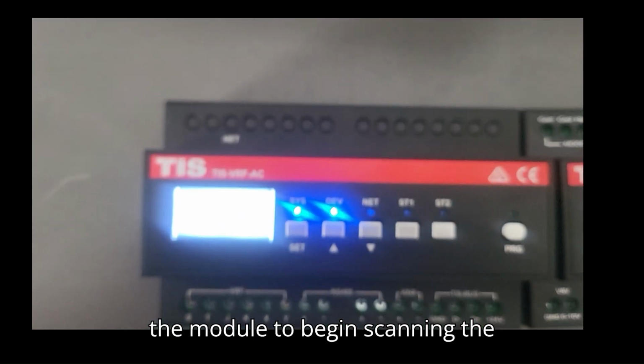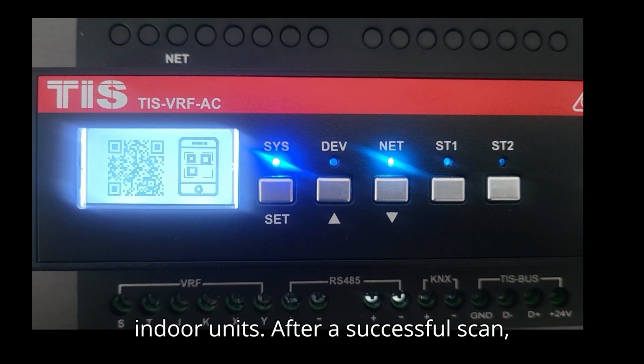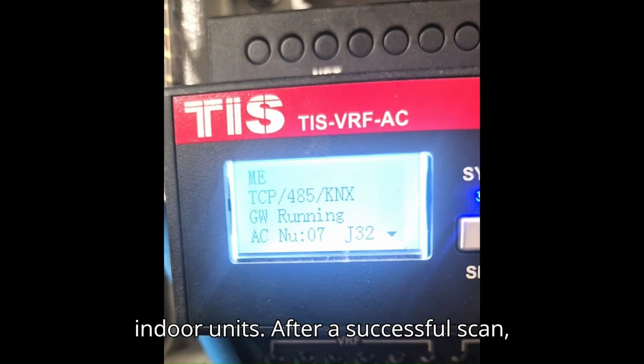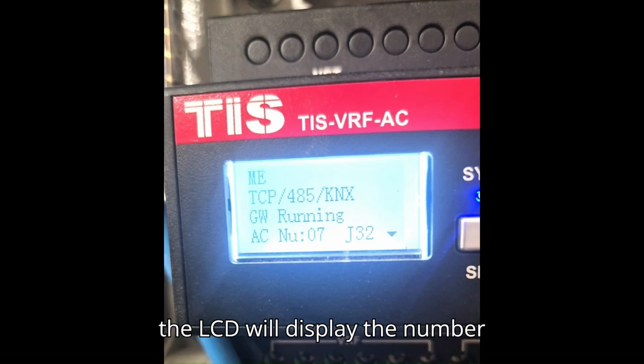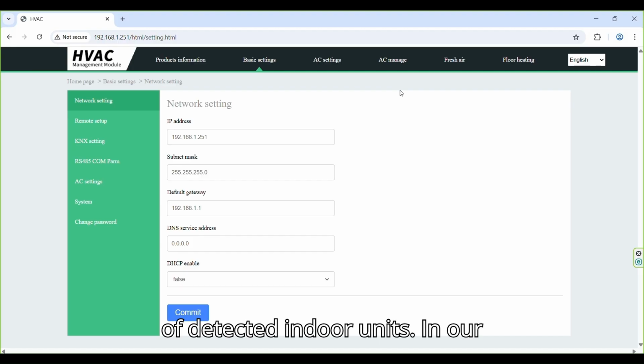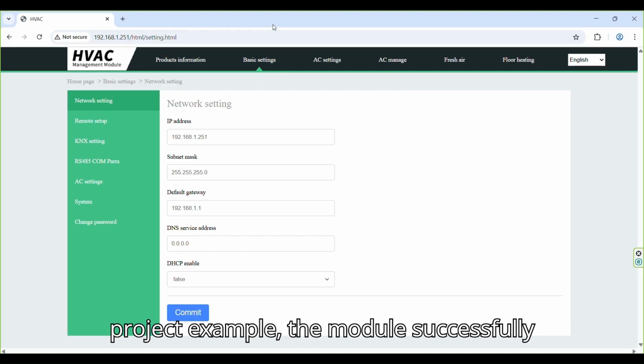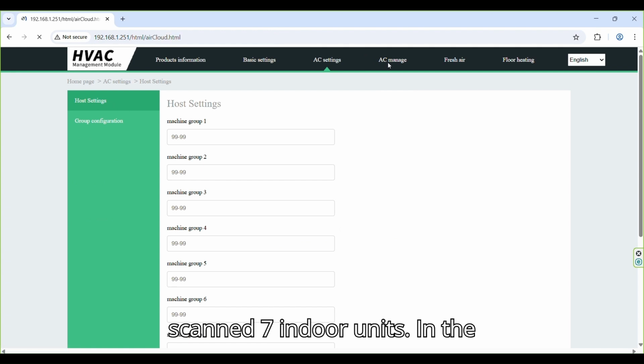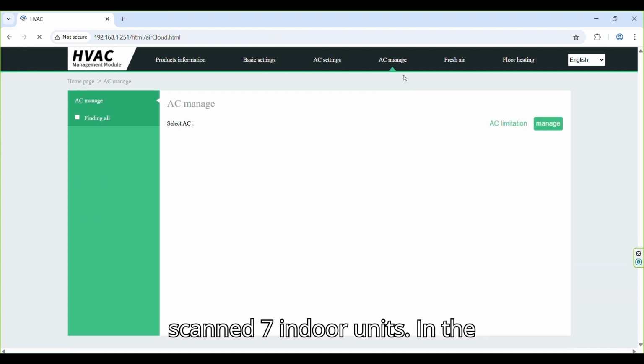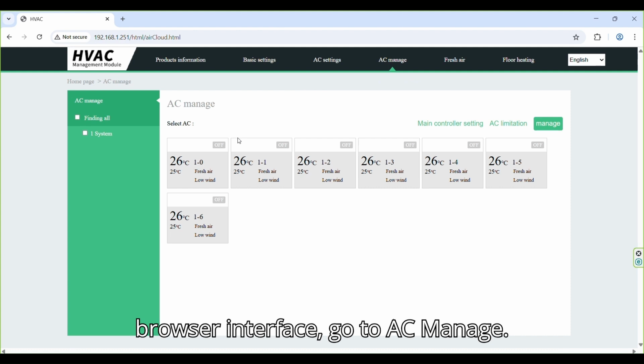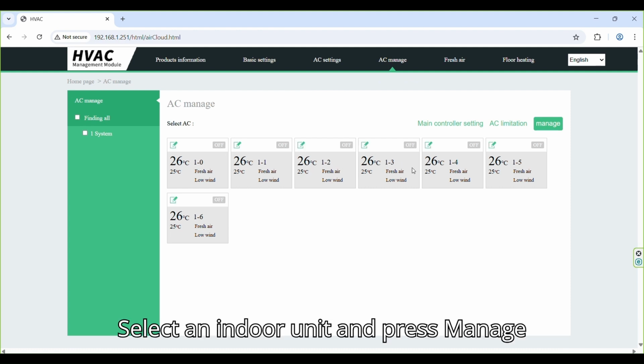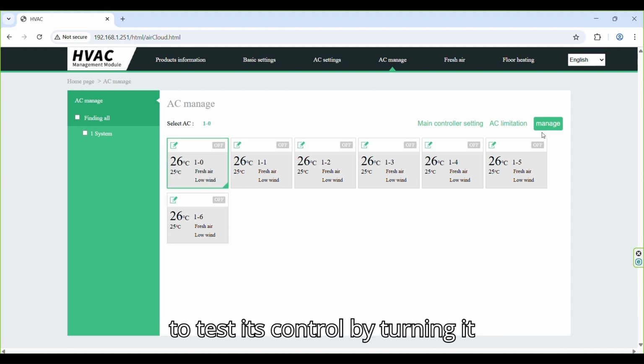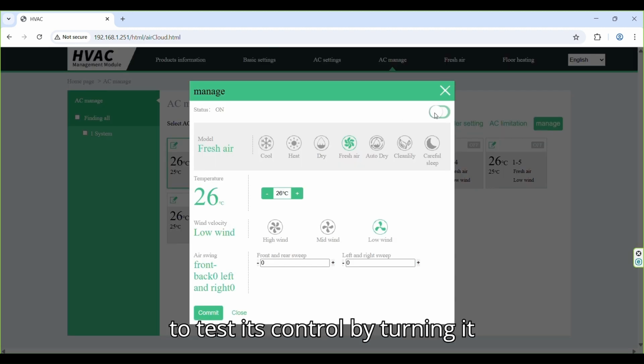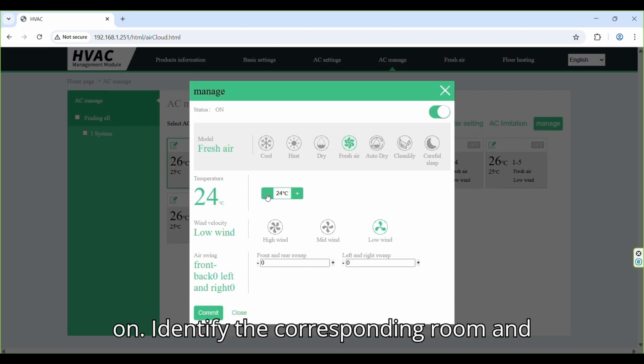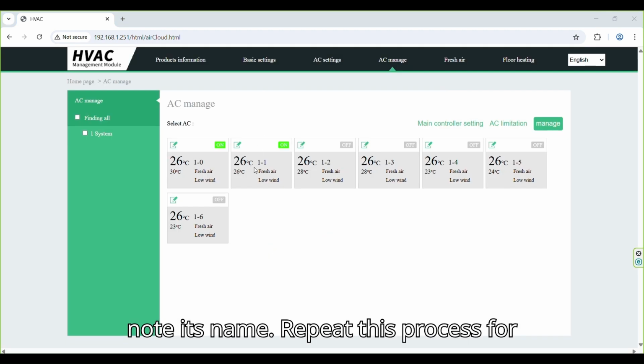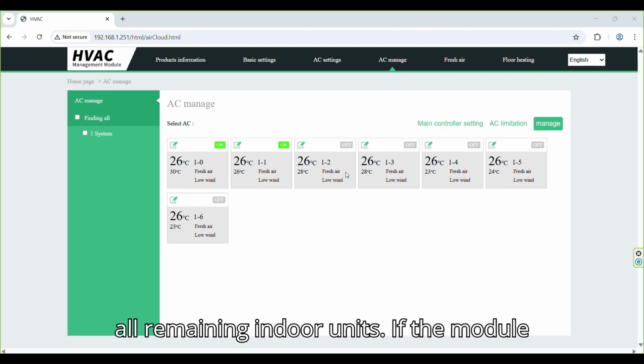Restart the module to begin scanning the indoor units. After a successful scan, the LCD will display the number of detected indoor units. In our project example, the module successfully scanned 7 indoor units. In the browser interface, go to AC Manage. Select an indoor unit and press Manage to test its control by turning it on. Identify the corresponding room and note its name. Repeat this process for all remaining indoor units.